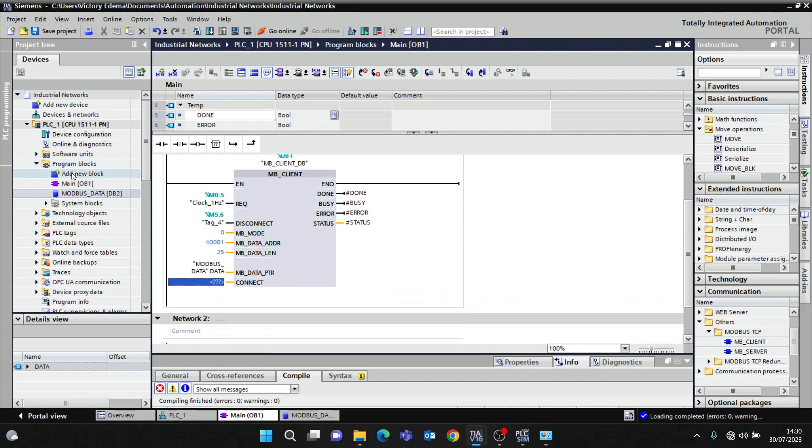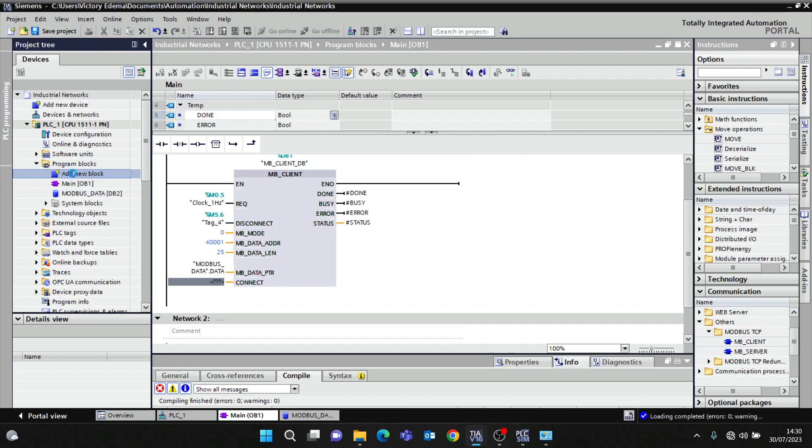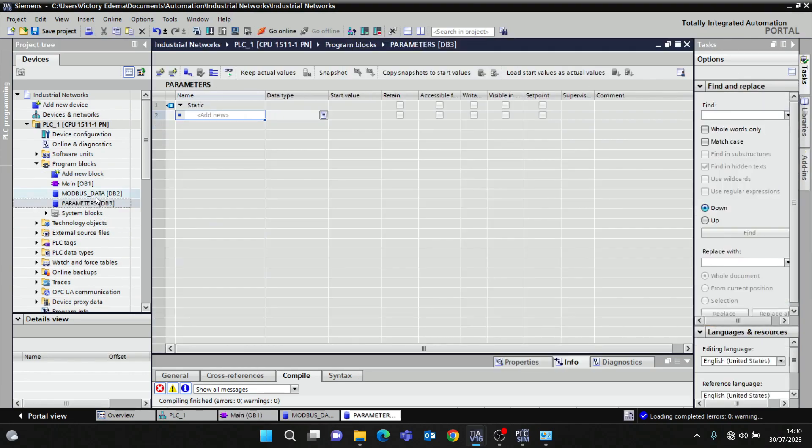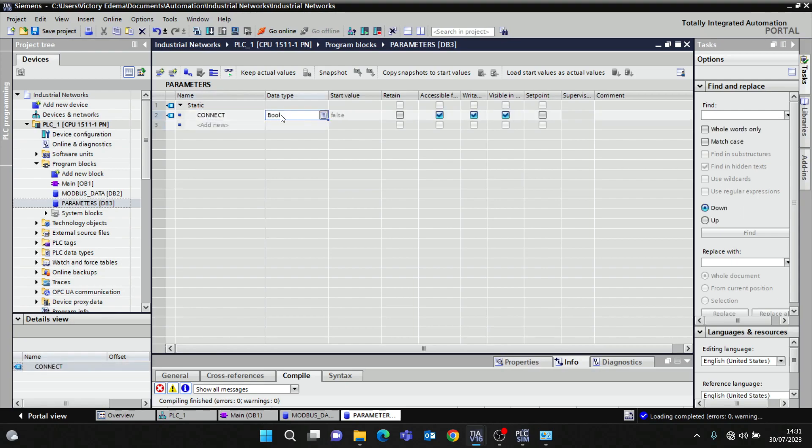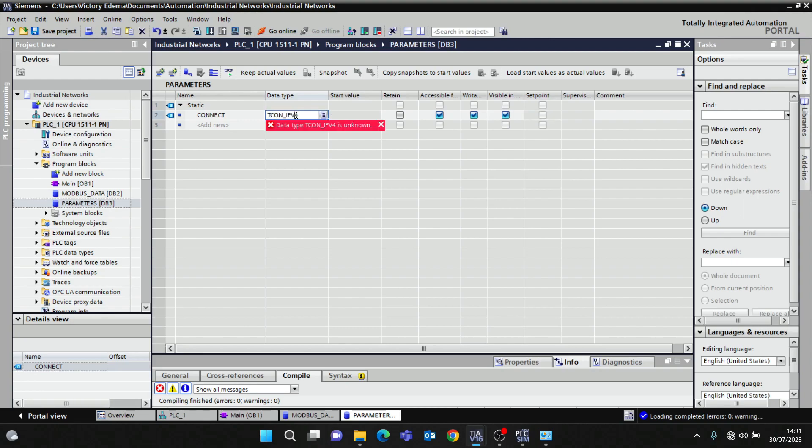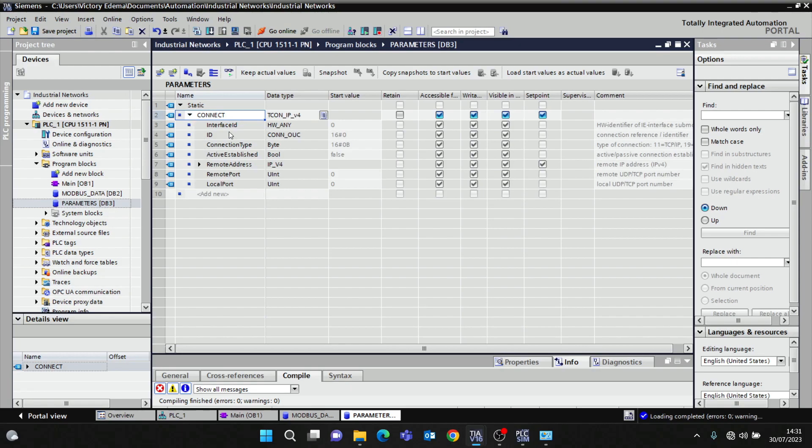MB_CONNECT - these are the connection parameters to my server. This is the client block, so what are the connection parameters that enable the client to connect with the server? I'll create another data block and call it parameters. I'll call it connect_params, and the data type for Modbus parameters in S7 is TCON_IP_v4.